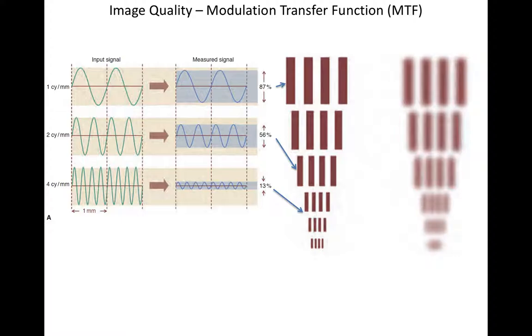This behavior is usually described as a modulation transfer function, which describes the behavior of the whole imaging system. Here's an example of a bar pattern where we have a spatial frequency in cycles per millimeter in the plane of the bar pattern, and that spatial frequency increases as you go farther down the pattern — more cycles per millimeter lower down than higher up.